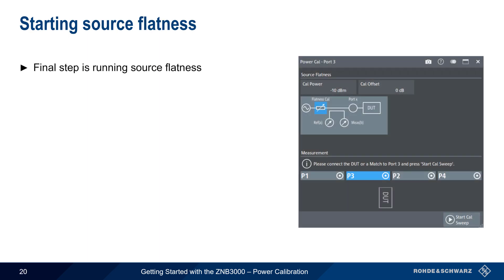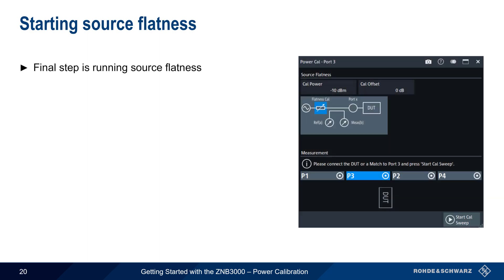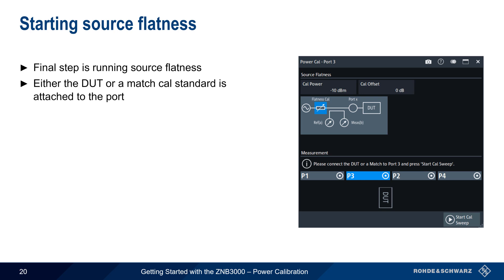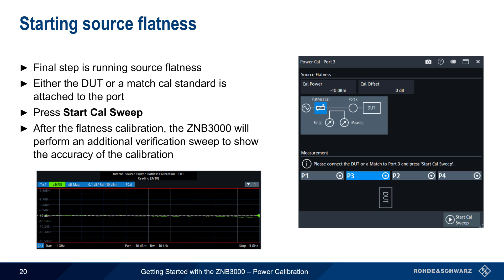The final step in power calibration is running source flatness. This can be done by either connecting the DUT to the port or by attaching a match calibration standard. Simply press Start Cal Sweep and follow the prompts. After the flatness calibration is completed, the ZNB3000 will perform an additional verification step to show the accuracy of the overall calibration.